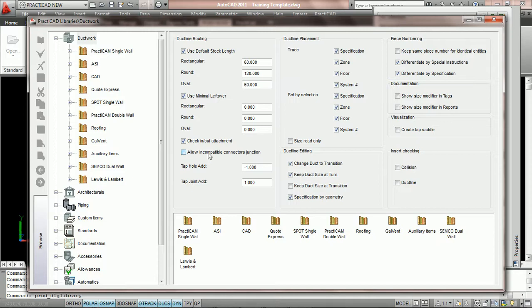When it's unchecked, we're not allowed to have incompatible connectors. So PractiCAD is automatically going to change the connections as you snap duct to duct. And it will only allow you to edit connectors that are compatible. Otherwise, every time you make one connection change, PractiCAD is going to change the connection you're attaching to it to whatever the compatible connector is.